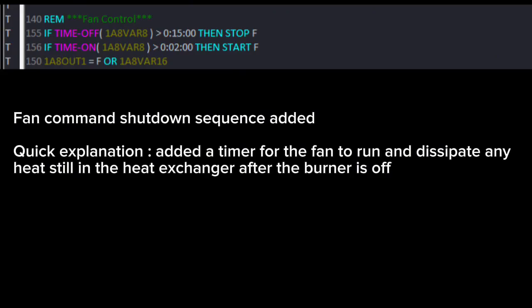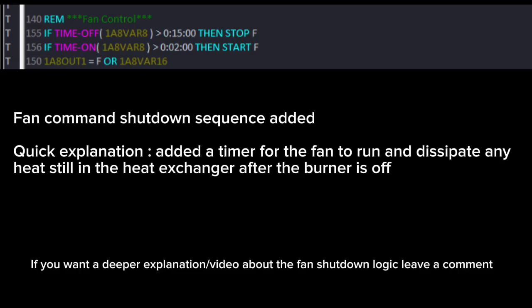So this is the logic I added. If you're curious or if you have any questions on what it is for or how it works, let me know. But essentially it's just a 15-minute rundown for the end of day schedule to stop the burner and let the supply fan run.